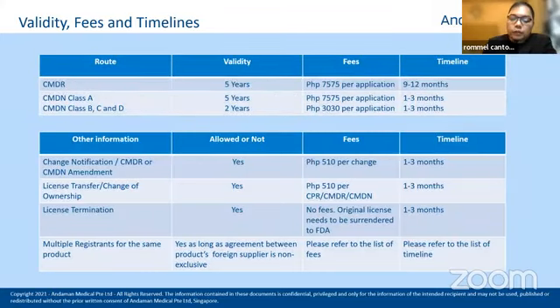So after knowing the process flow, we need to know what is the validity of each issued certificate, government fees to be paid, and timelines of approval. In the CMDR route, validity is 5 years with a fee of 7,575 pesos per application, with a 9 to 12 months timeline of application processing based on experience. For CMDN Class A, the validity is 5 years, fees of 7,575 pesos per application with 1 to 3 months timeline of application processing. For CMDN Class B, C, and D, the validity is 2 years. Fees is 3,030 per application with 1 to 3 months timeline of application processing.